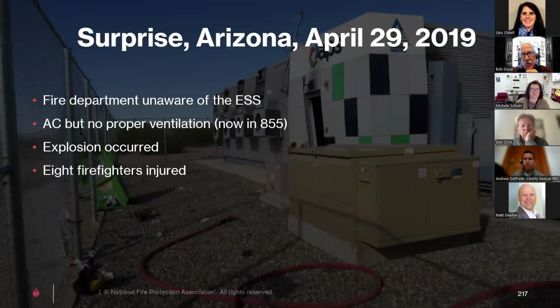Eight firefighters were injured, four seriously enough to be flown to local trauma centers. Multiple investigations, which I'll cover briefly, found there was a thermal runaway in the batteries inside the enclosure that triggered the gaseous suppression system based on heat. Once that went off, it only slowed the process down — the fire continued to burn inside the enclosure, and the atmosphere got too rich. But when the fire department opened the door to investigate further, enough fresh air came in to create an explosive atmosphere, which exploded and injured the firefighters.